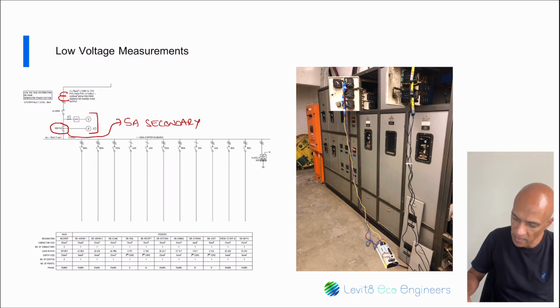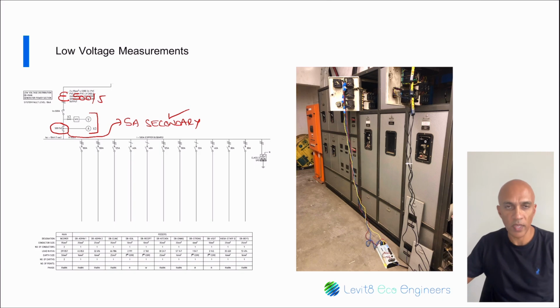So you could either bring your own current clamp with a 500 to 5 ratio or higher, or you could use the secondary of the panel CTs that are on this panel, and you have a 500 to 5, and you could connect to this 5 amp and you can use your transducer to get the readings.